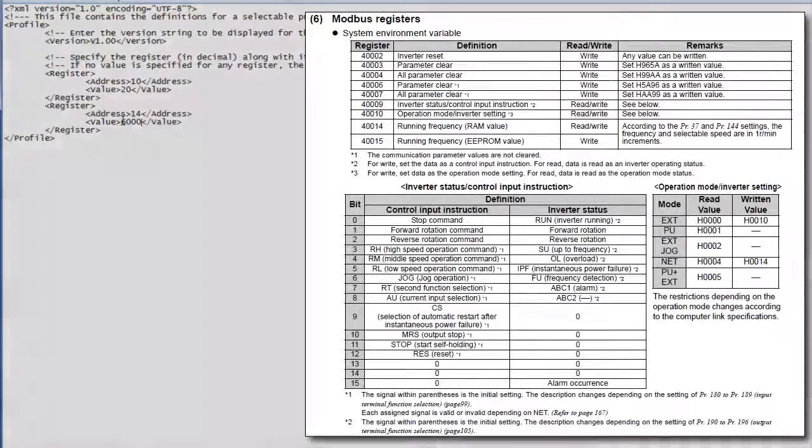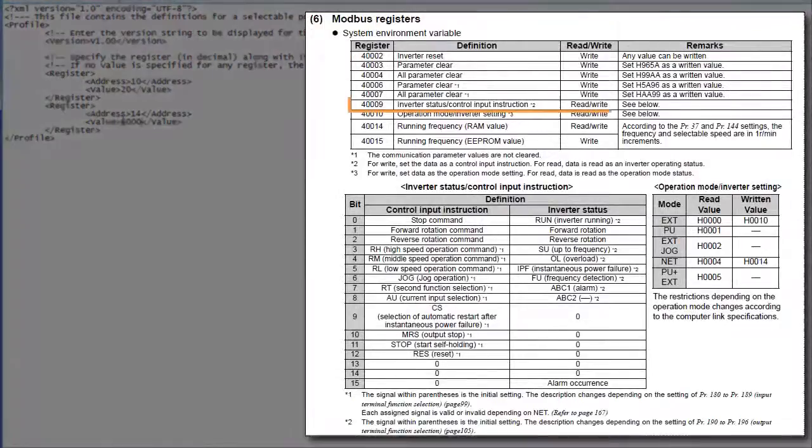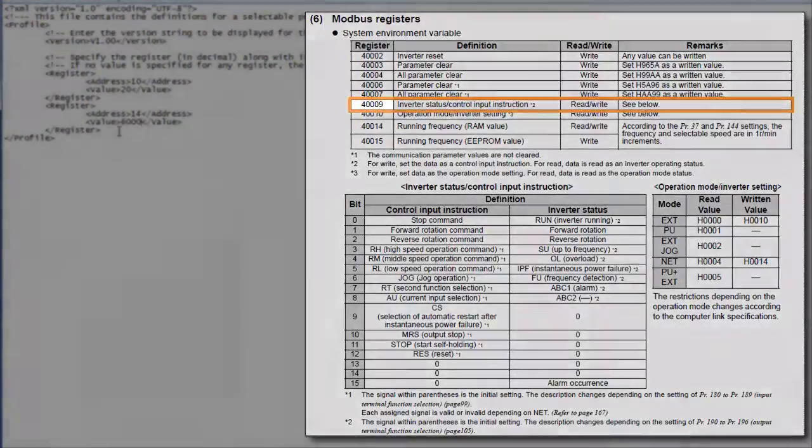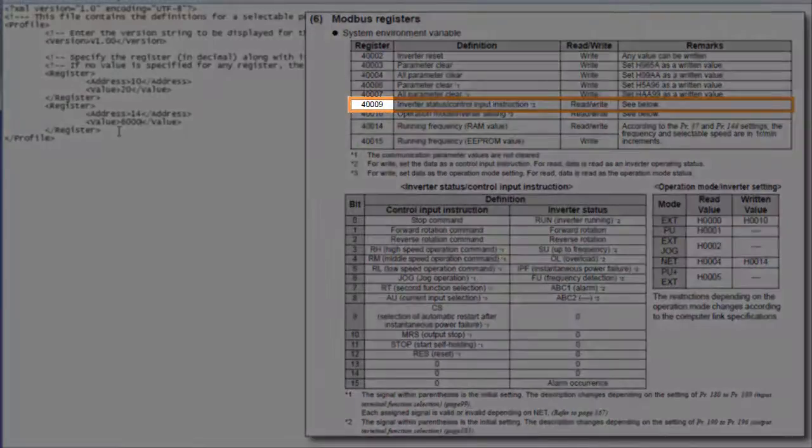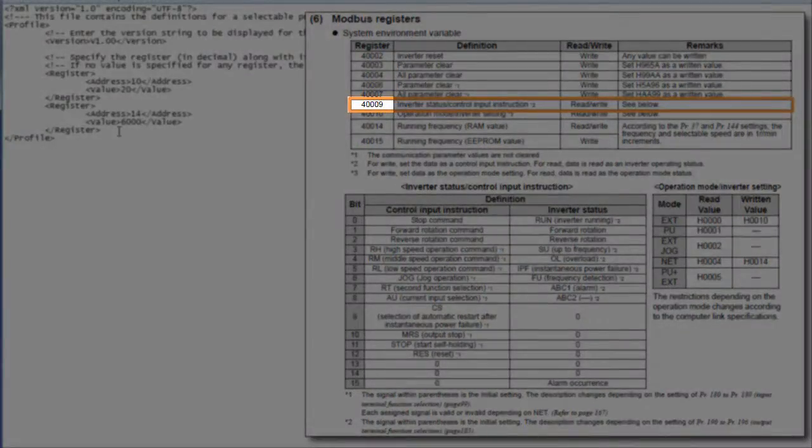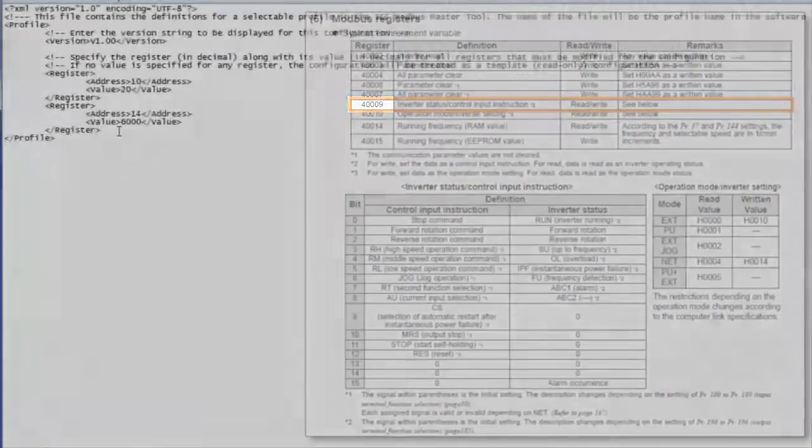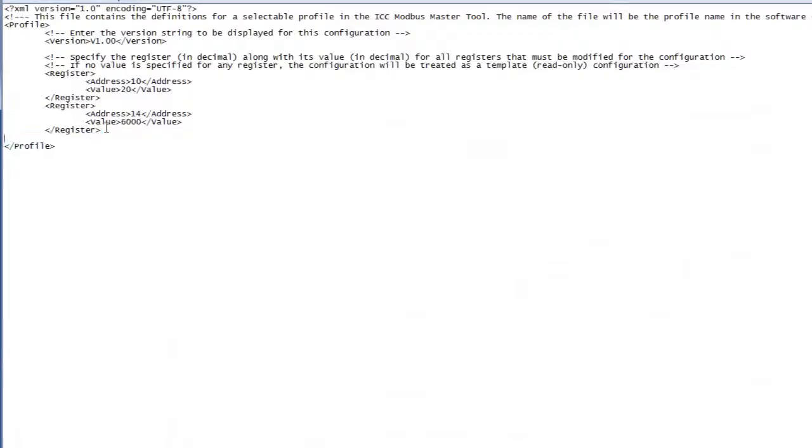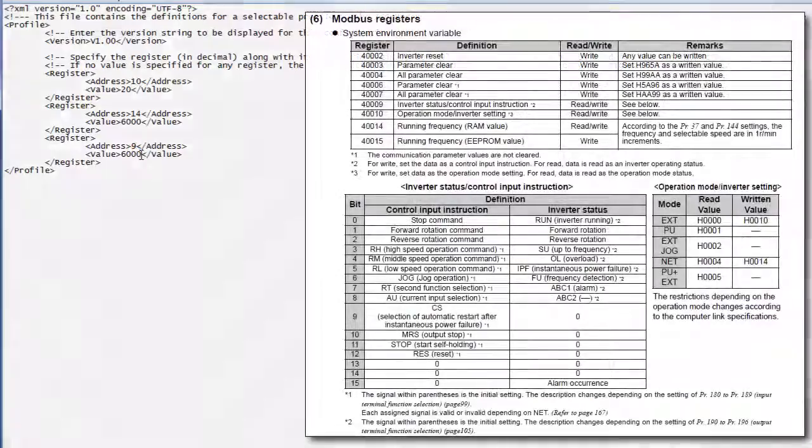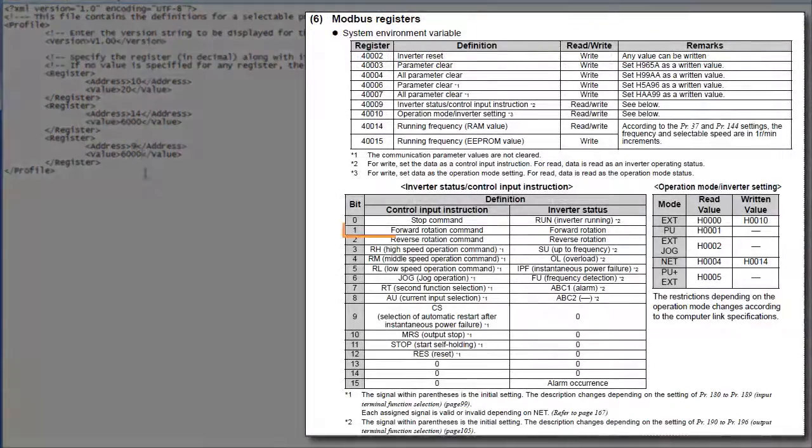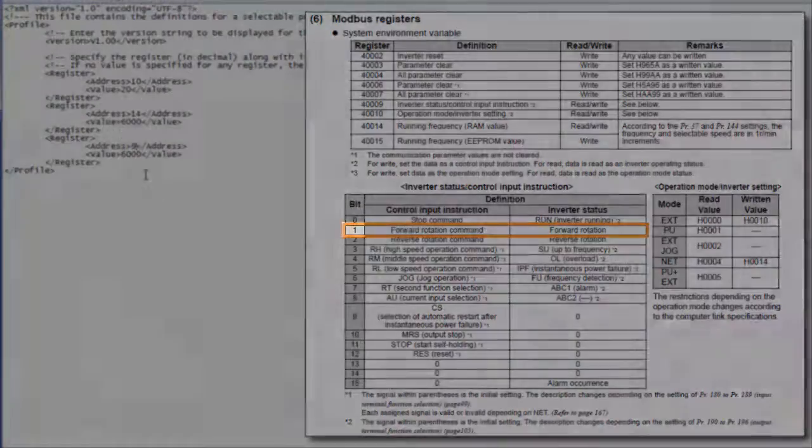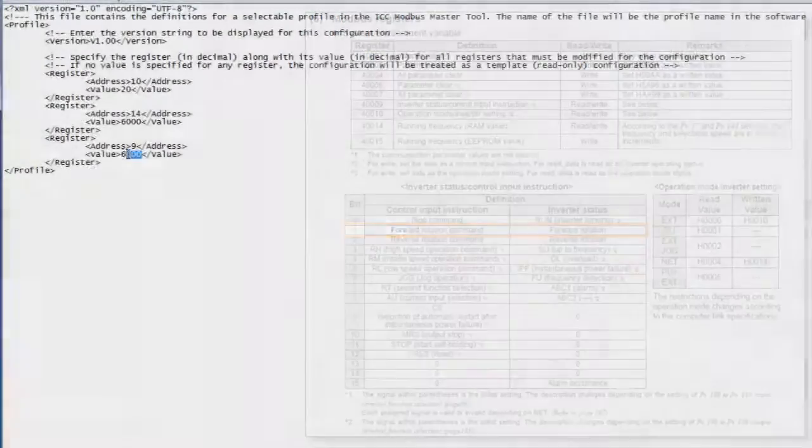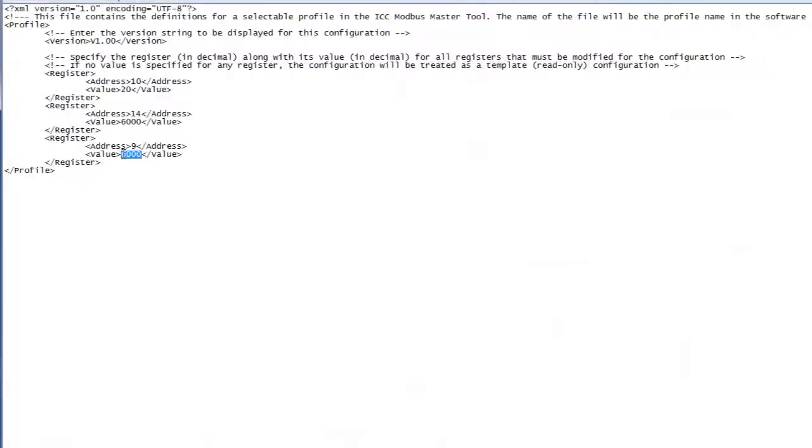The last parameter we need to set is the control input instruction to make the inverter run. The register for it is 40,009, which is holding register 9. Again, we'll copy and paste our last register definition. And we'll enter 9 for our last register's address. The bit we want to set is the forward rotation command, which is bit 1. This equates to a decimal value of 2. So we'll enter 2 for the register's value.